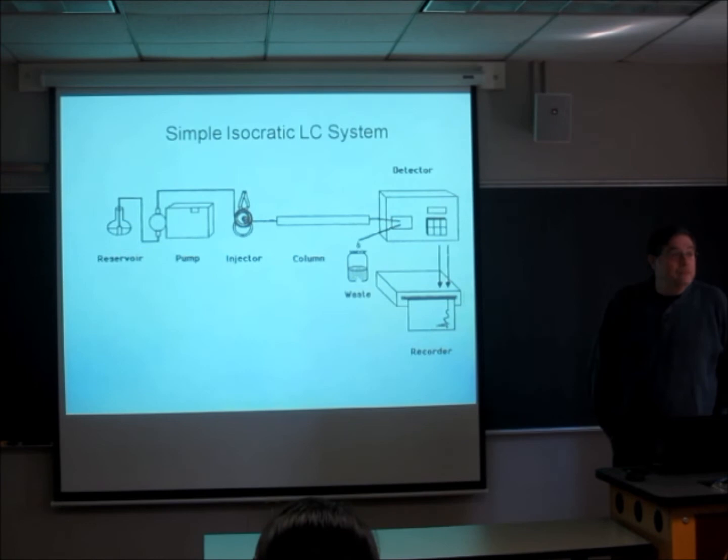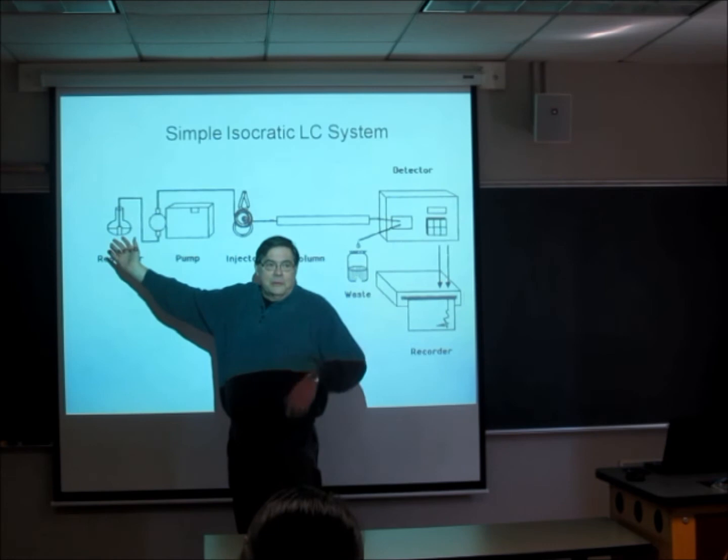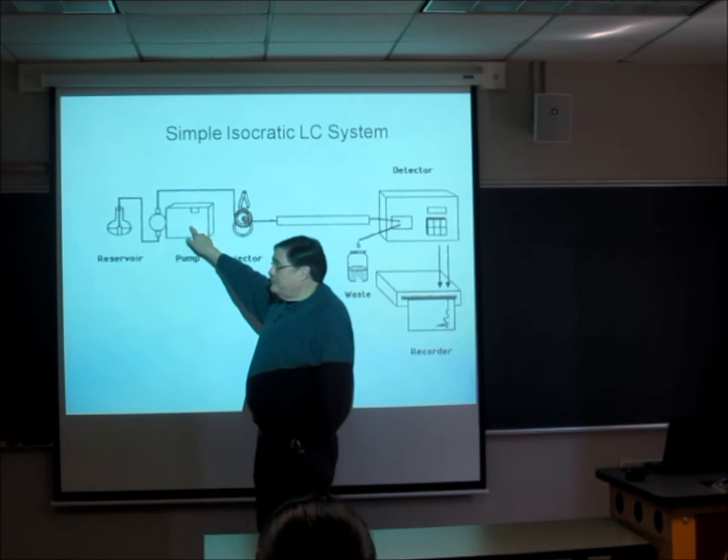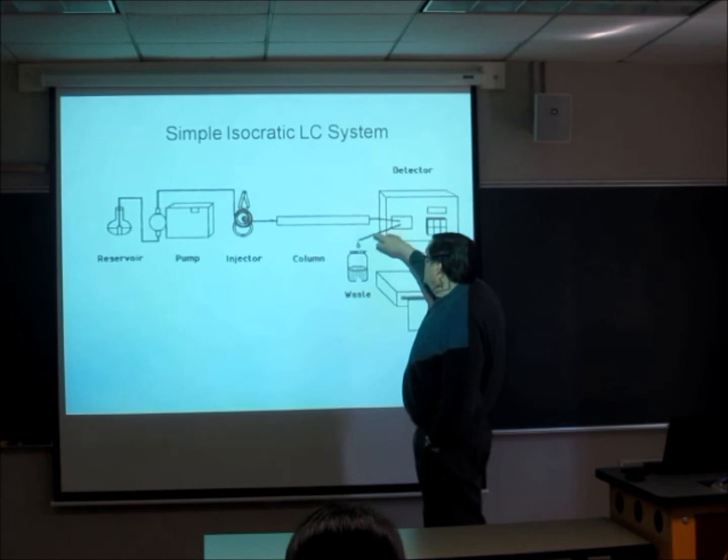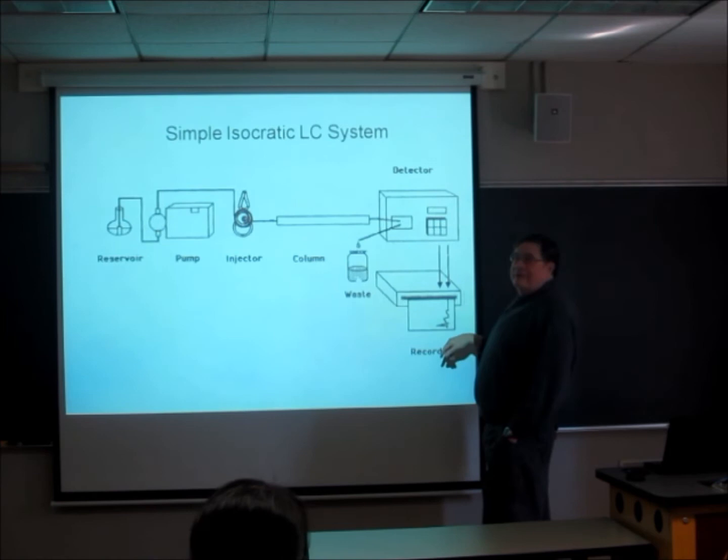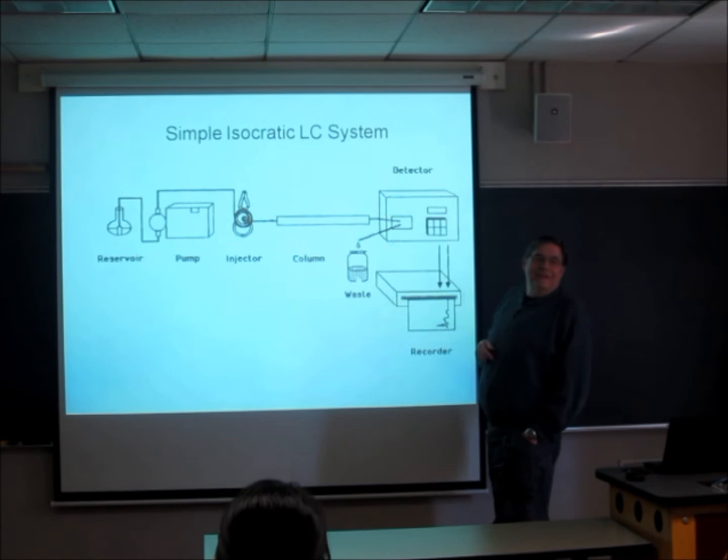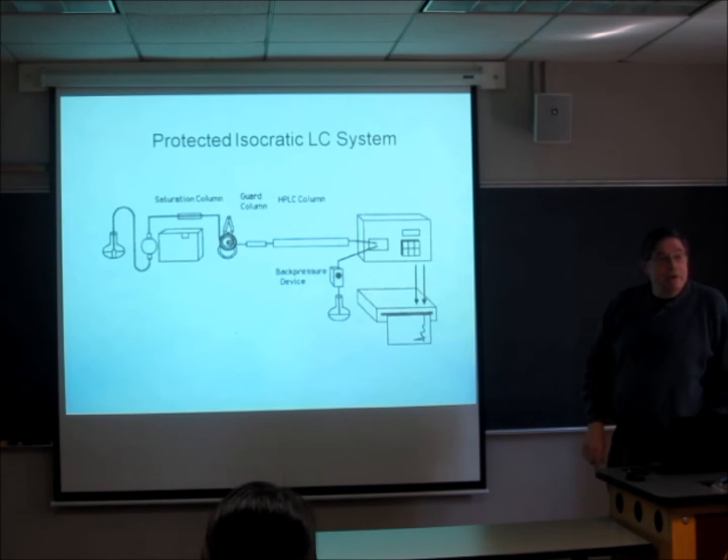Here's probably the oldest picture that Pete could find of a simple isocratic LC system. You can use mixed solvents. It doesn't have to be just water or just methyl alcohol. It can be something mixed up 50-50, something like that. Whatever it is, you don't change it. You take that solvent from the reservoir and you pull it with a pump and push it. Take it through an injection loop, then press the material through the column to a detector, to a waste container. The detector picks up a signal and back when this was a real good example, a strip chart recorder would take the detected signal.